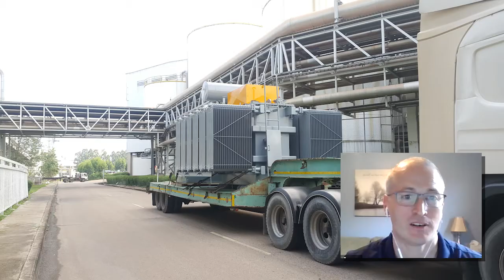The last thing I want to talk about is commissioning, when the transformer actually comes in and is transported. It goes back to that spec again, because the transformer spends the vast majority of its life sitting still, not moving. The time it really spends moving and subject to things that could damage it is during transportation. So you want to make sure it's spec'd out properly, that it can handle the voyage from wherever the manufacturer is to wherever you need the transformer.